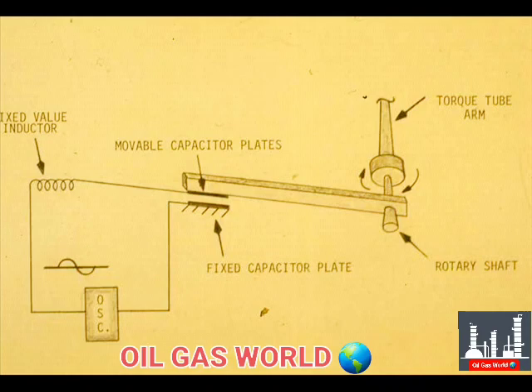This drawing schematically illustrates the capacitance type of rotary shaft position detector. A series LC circuit composed of a fixed inductance and a variable capacitor is electrically connected to the output of an oscillator. In this example, the movable plate moves when the torque tube moves. Assume the circuit is at resonance.